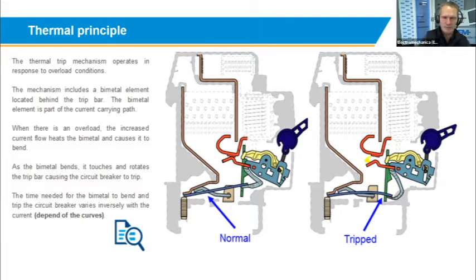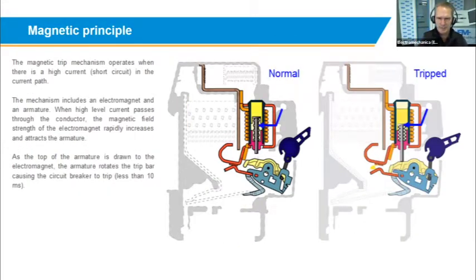Then, as I said, we talk about the thermal, and then there's also a magnetic part or magnetic technology inside the circuit breaker. So what is the magnetic part of the circuit breaker? Magnetics is what we talk about as the short circuit protection of the circuit breaker. On short circuit, the magnitude of the fault going through a circuit breaker is huge, and you need to disrupt that current as fast and as effectively as possible. That's where they use the magnetic principle inside the product.